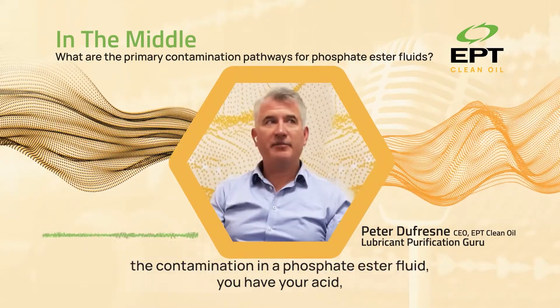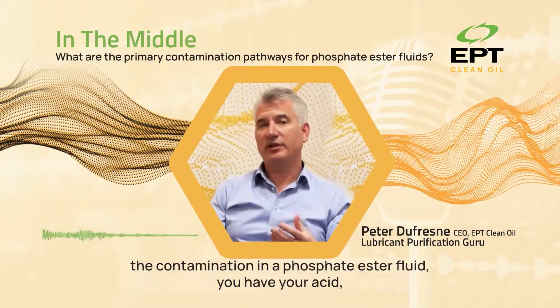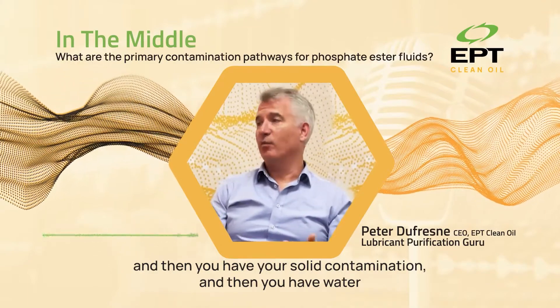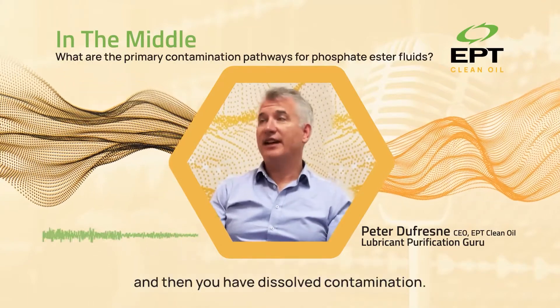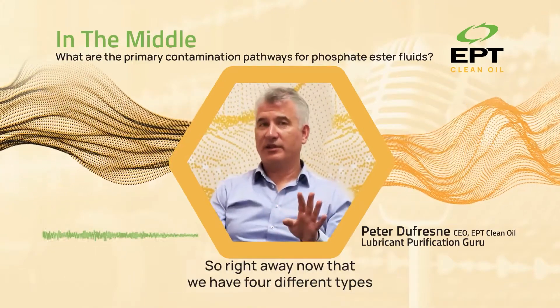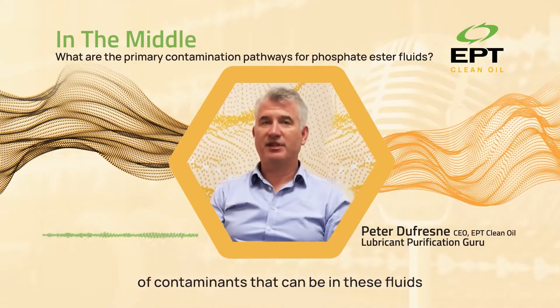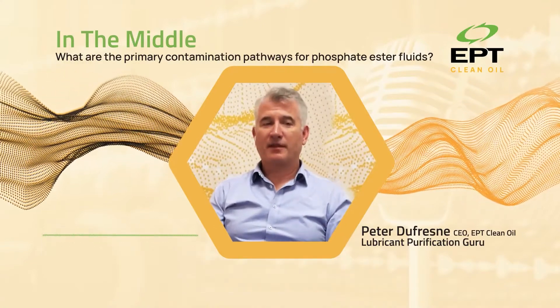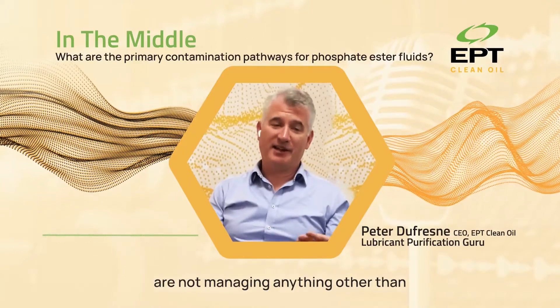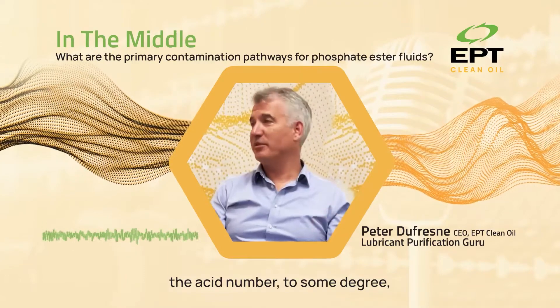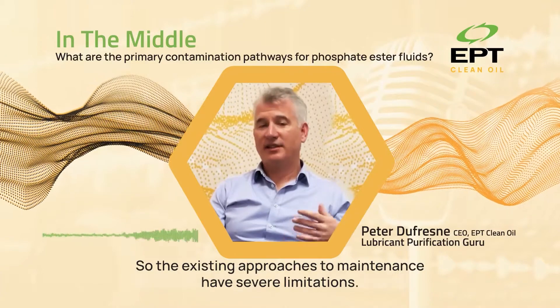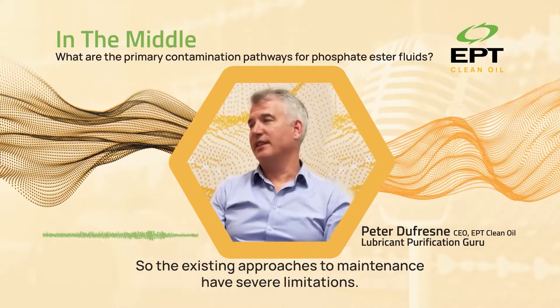Generally, if you're going to classify the contamination in a phosphate ester fluid, you have your acid, and then you have your solid contamination, and then you have water, and then you'd have dissolved contamination. Now that we have four different types of contaminants that can be in these fluids, you'll find that existing systems are not managing anything other than the acid number, to some degree, and the solid contamination, to some degree. So the existing approaches to maintenance have severe limitations.